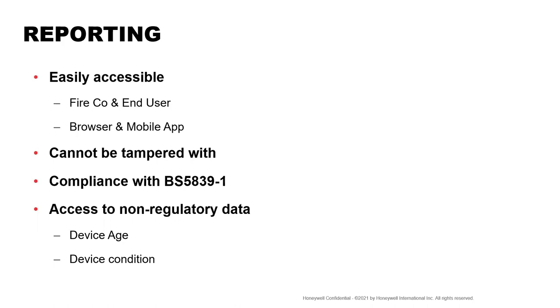We hear a lot as a manufacturer, I get people phoning me saying, I'm the owner of a building and my service and maintenance company are telling me that they need to change all the detectors in my building. How do I know? There doesn't appear to be anything wrong with them. With the information that we're now giving the end user directly, he can see the device age. He can see 5839 part one, the recommendation. It doesn't need anybody outside of that to explain to that end user that he needs to change it. It's in front of him.